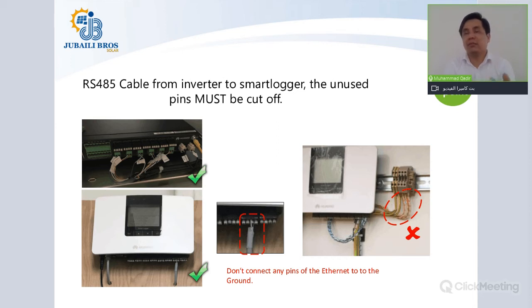When you're using an Ethernet cable, there are 8 different wires, but only 2 of them carry the data, the blue and the white blue wires. The rest of the wires, the orange, green and white ones, you will have to cut properly and insulate using heat shrink sleeves or tape so that it looks clean at the smart logger end. You do not need to do any earthing of the wires which are not being used in connection to the smart logger, so you're not advised to do so.